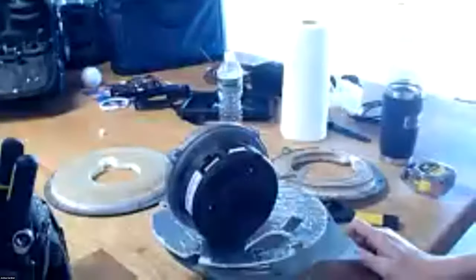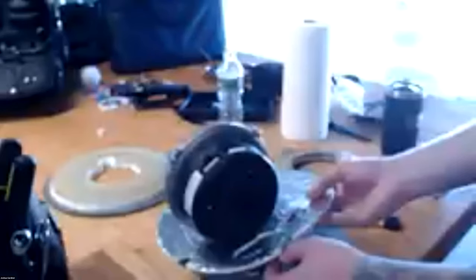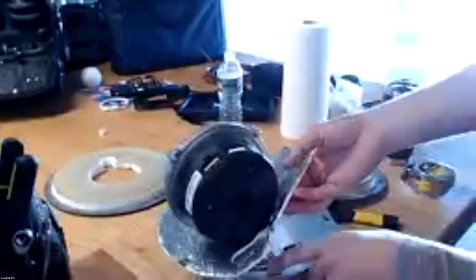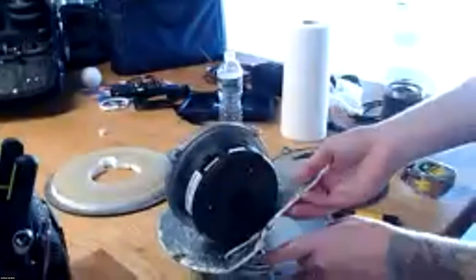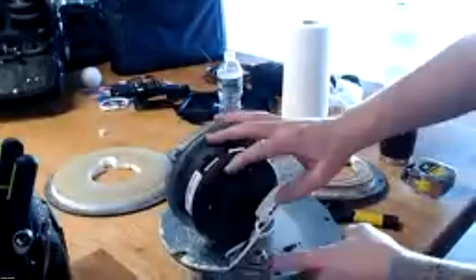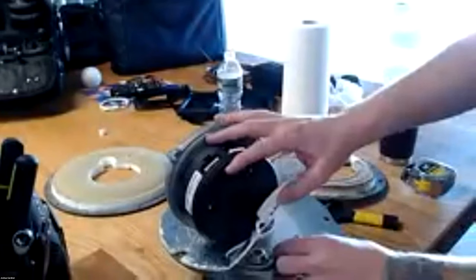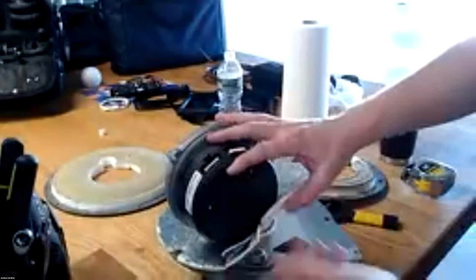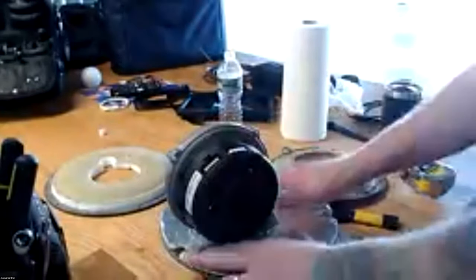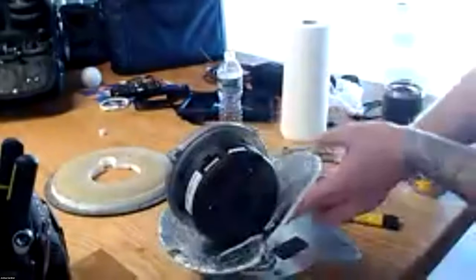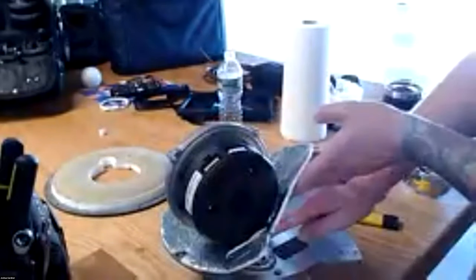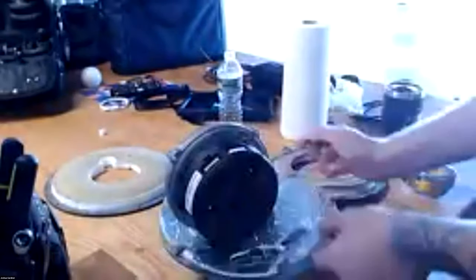If you get an igniter, you're going to get new gaskets and all that, but check your gasket. Make sure you don't see any signs of leakage around your sight glass and also the igniter gasket. So if you're gonna change the igniter, it will come in with a new gasket, so that's fine. And then just look around the fan, make sure you don't see any signs of leakage coming through the fan and the fan gasket.